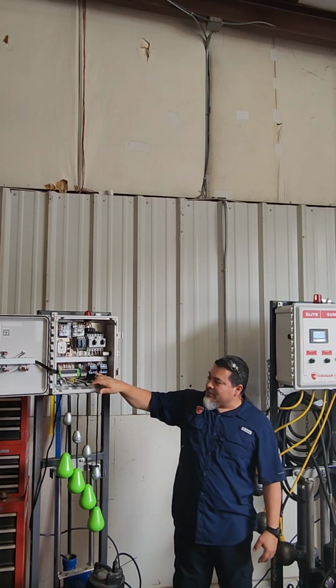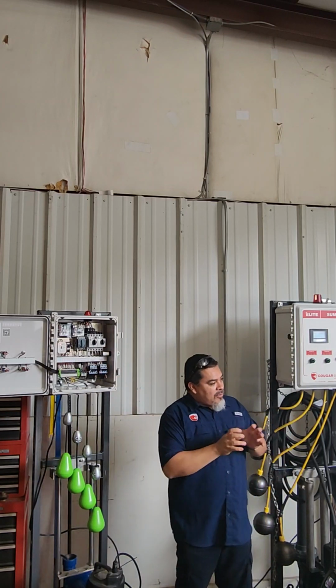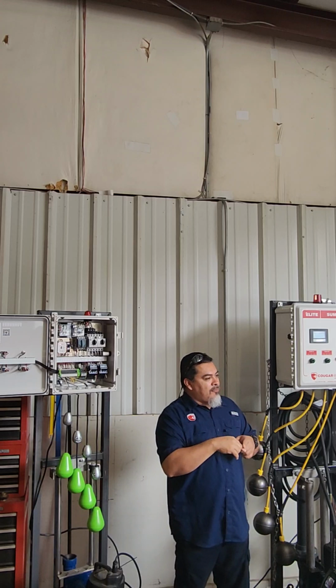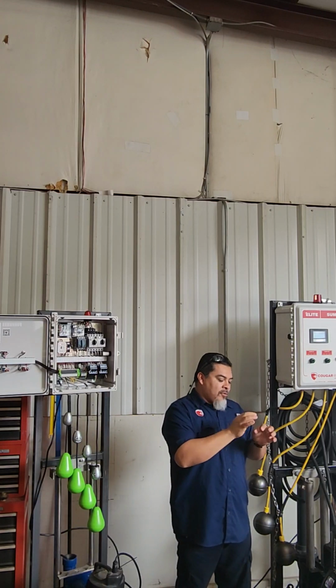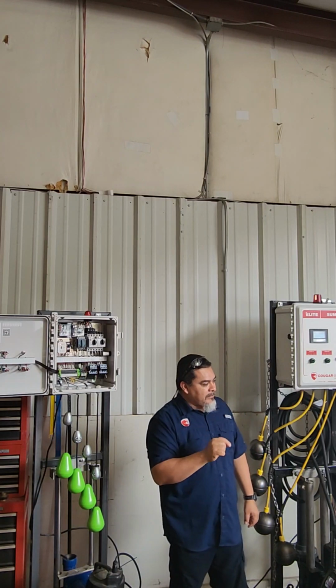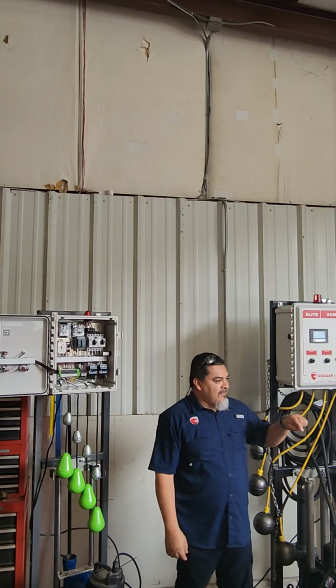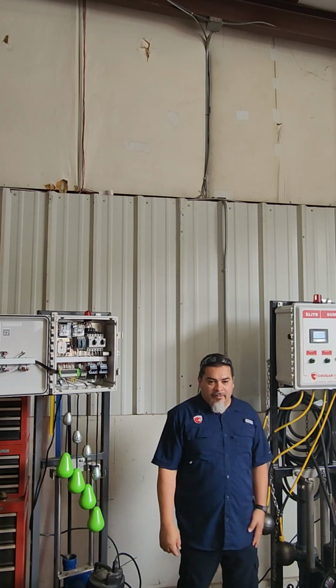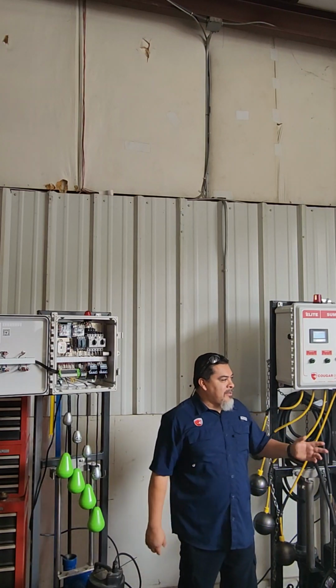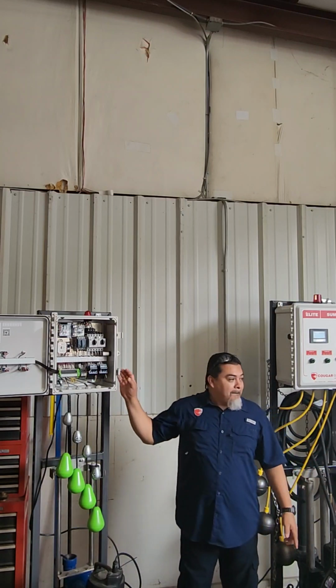You have another one that looks similar to these, and they have the overload at the bottom. It has a blue and a red little button, and of course a little window that might have a little T for trip. Always look into that and see if that is the trip before you go on and say that the pump ain't coming on. Do y'all make those windows bigger?